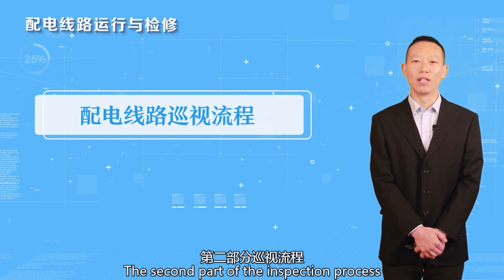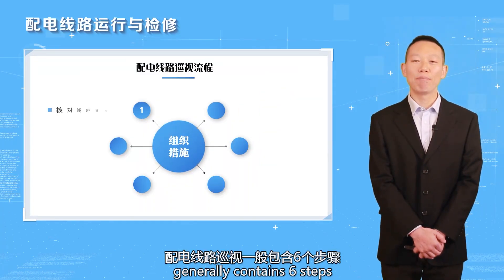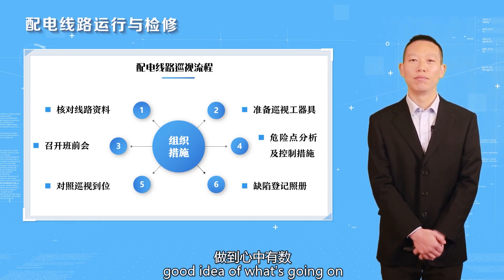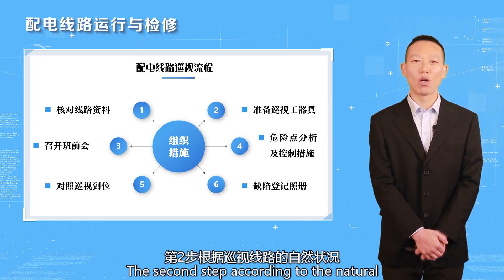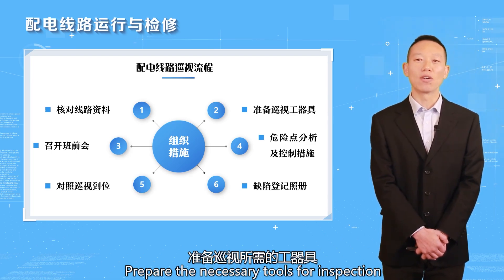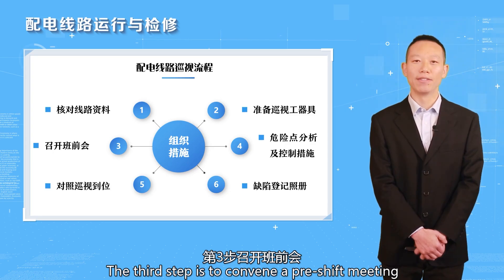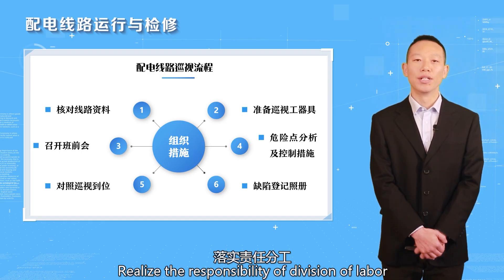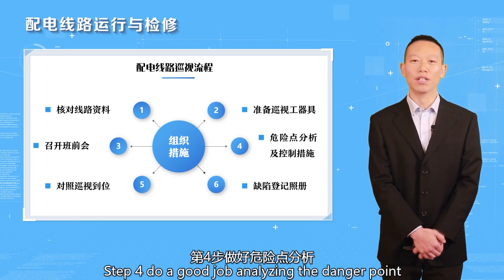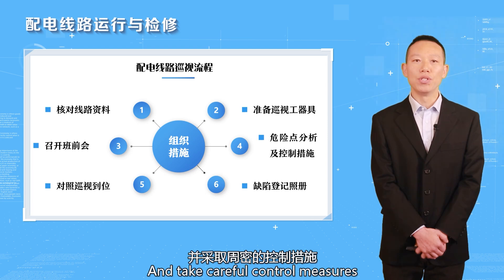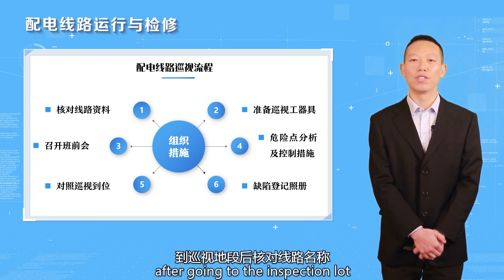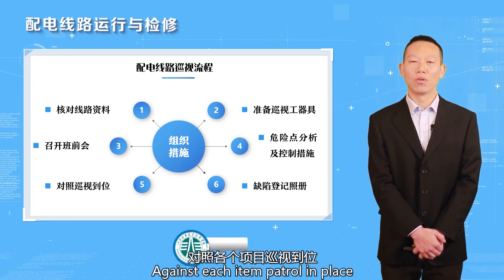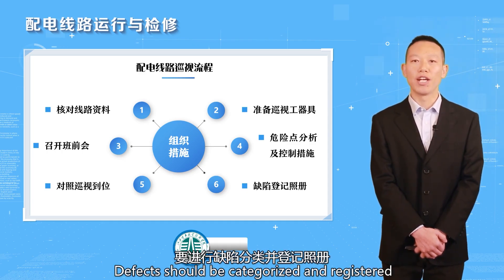Distribution line inspection generally contains six steps. Step 1: check the technical data of the inspection line to make sure you have a good understanding of conditions. Step 2: prepare the necessary tools for inspection according to the natural conditions of the line. Step 3: convene a pre-shift meeting to explain the scope and contents of inspection and assign responsibilities. Step 4: analyze the danger points and take careful control measures. Step 5: after arriving at the inspection site, confirm the line name and scope, patrol each item in place. After the final inspection, defects should be categorized and registered.